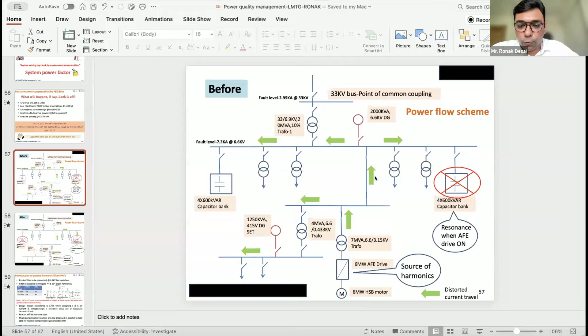Sorry, APF. Actually, I think the previous case was a very nice scenario to look into. We have to understand that there are two types of solutions available for harmonics: one is the passive filter, another is the active filter. These are customer-side solutions. On the customer side, we first have to decide whether the harmonics are fixed or variable. If it is a fixed harmonic, then we can install a passive filter and solve the problem. But if the load is varying and the harmonics are also varying, that means sometimes the third harmonic is high, sometimes the fifth, sometimes the seventh, then you cannot install a passive filter. You have to go to the active filter.